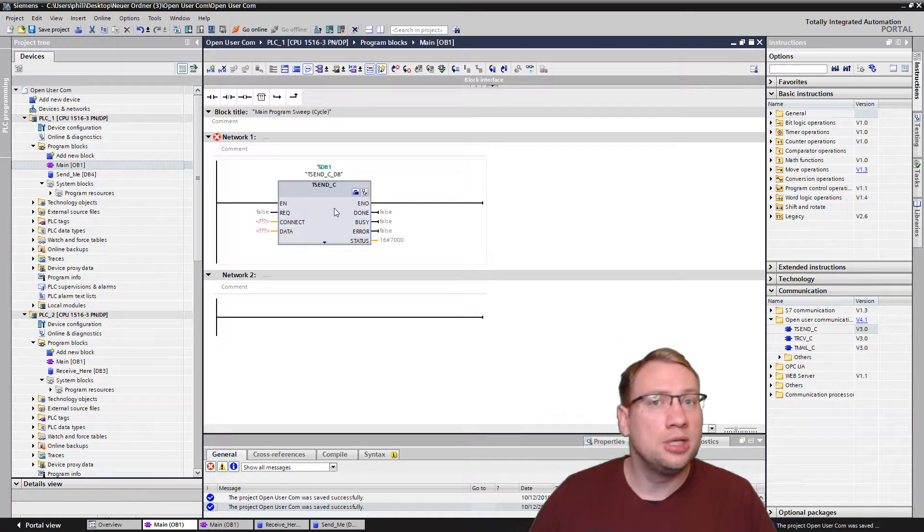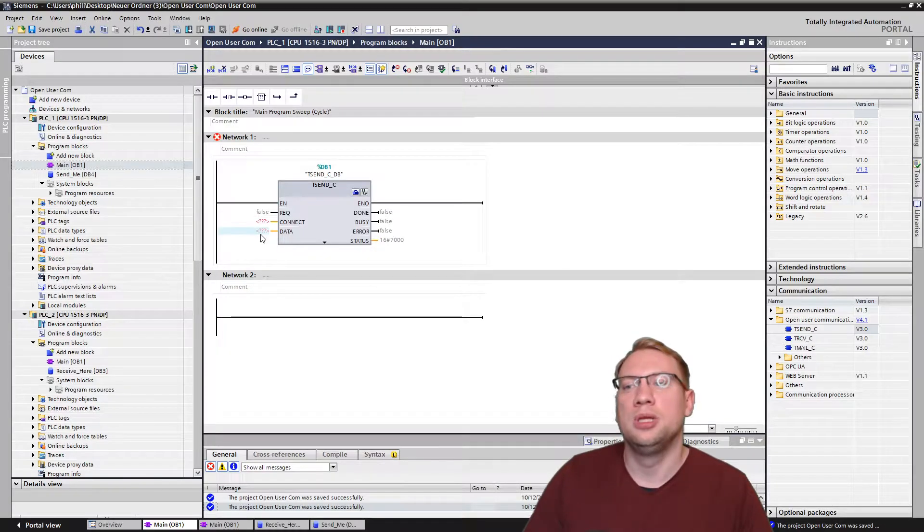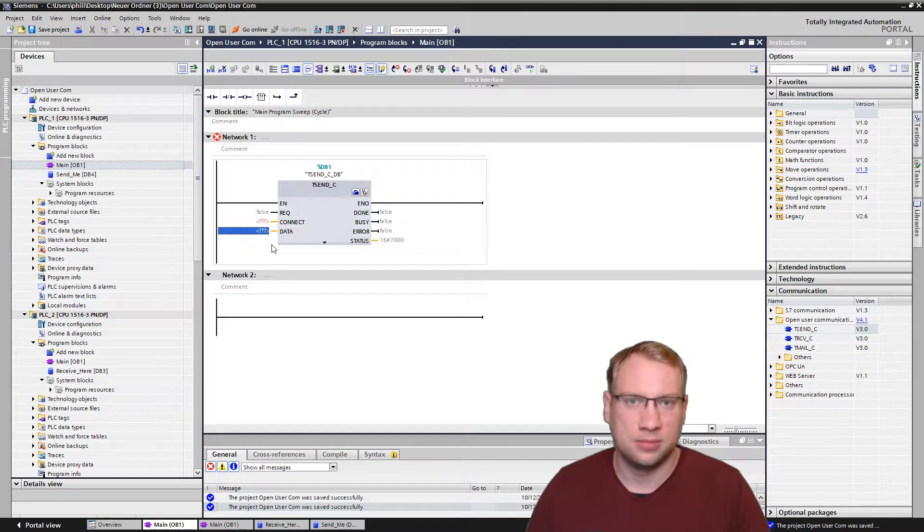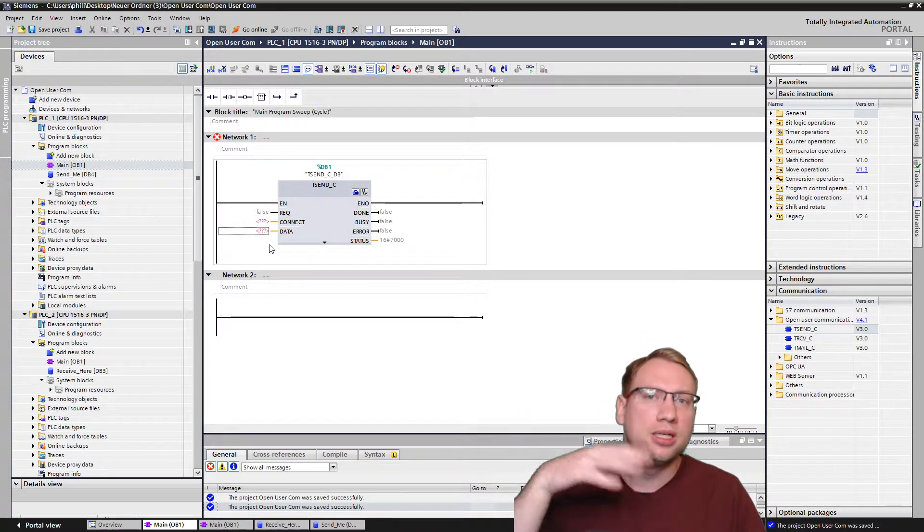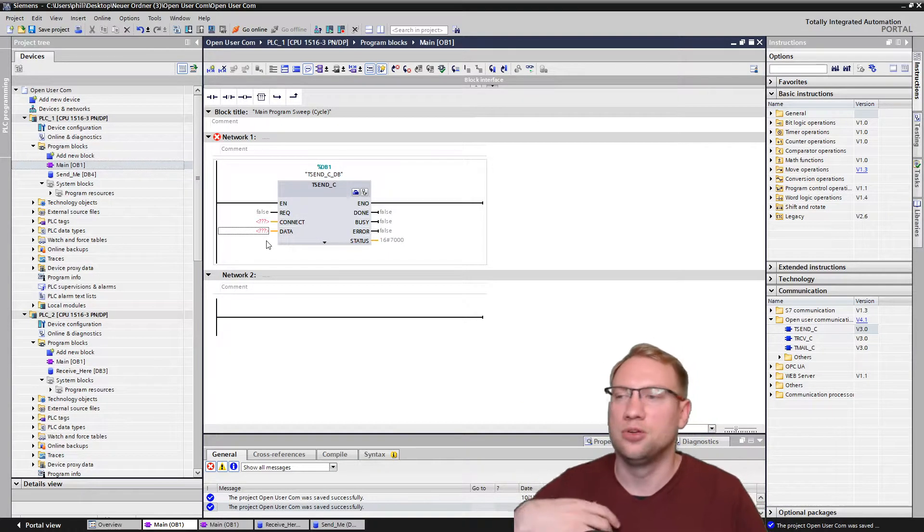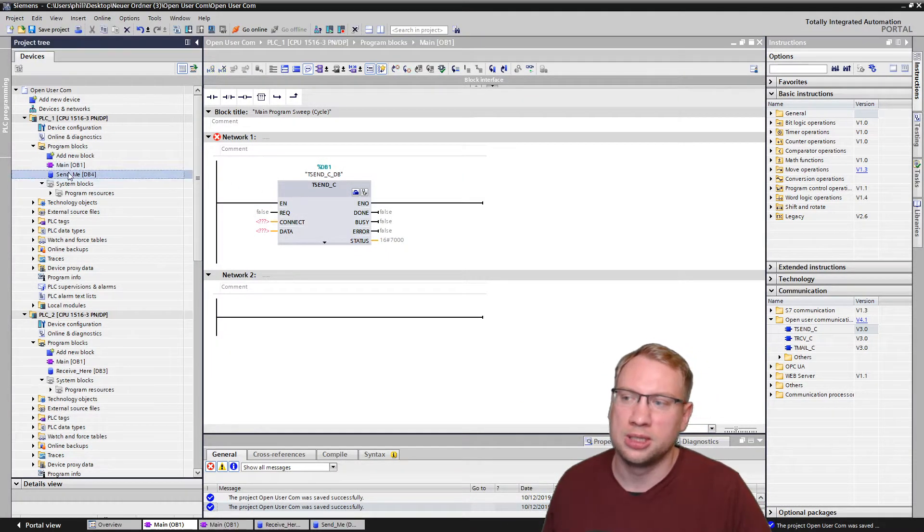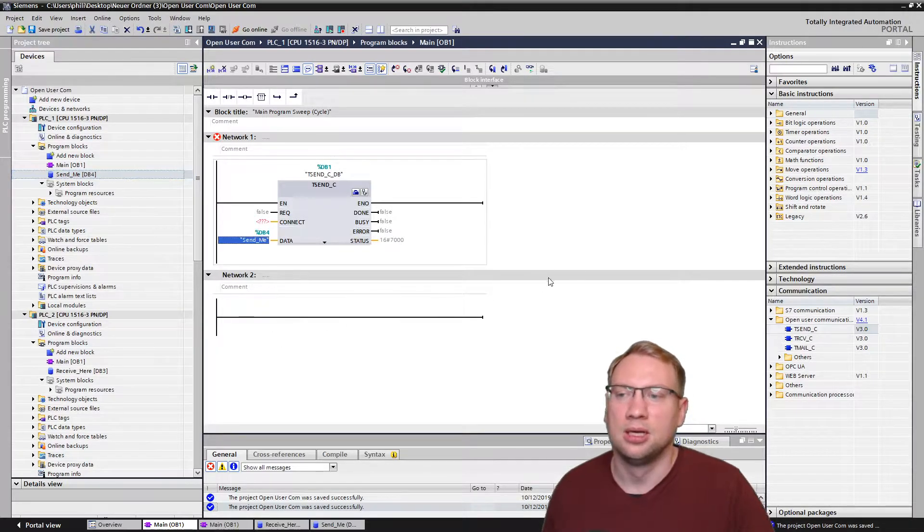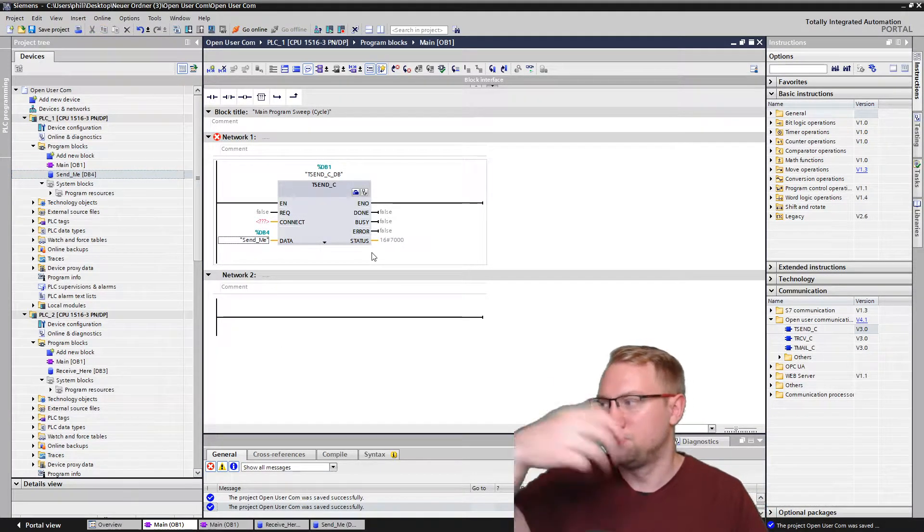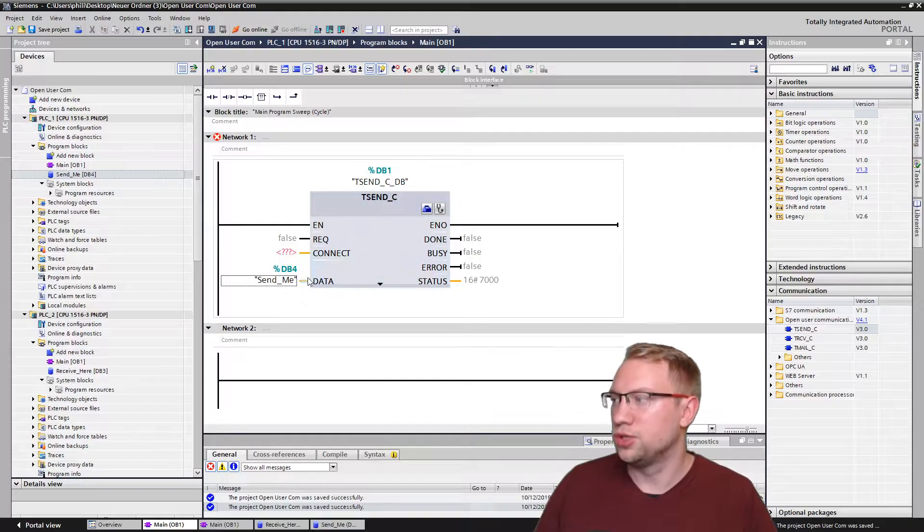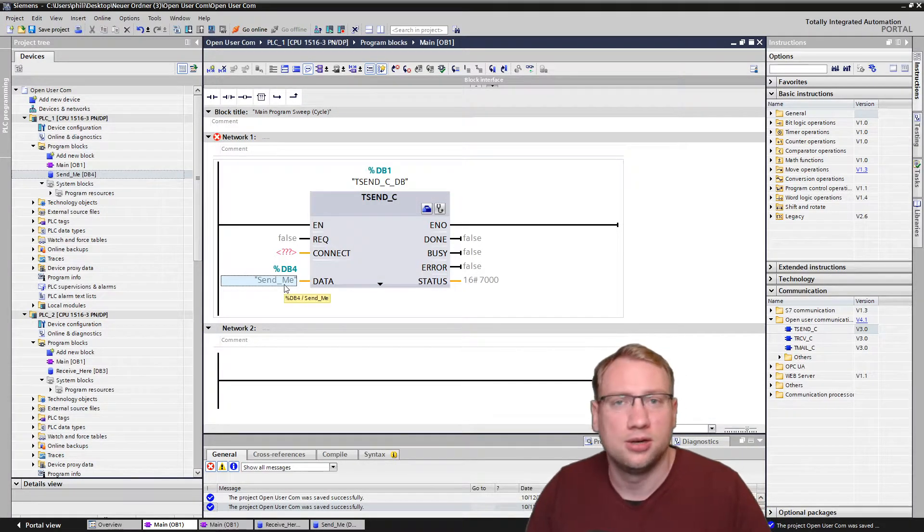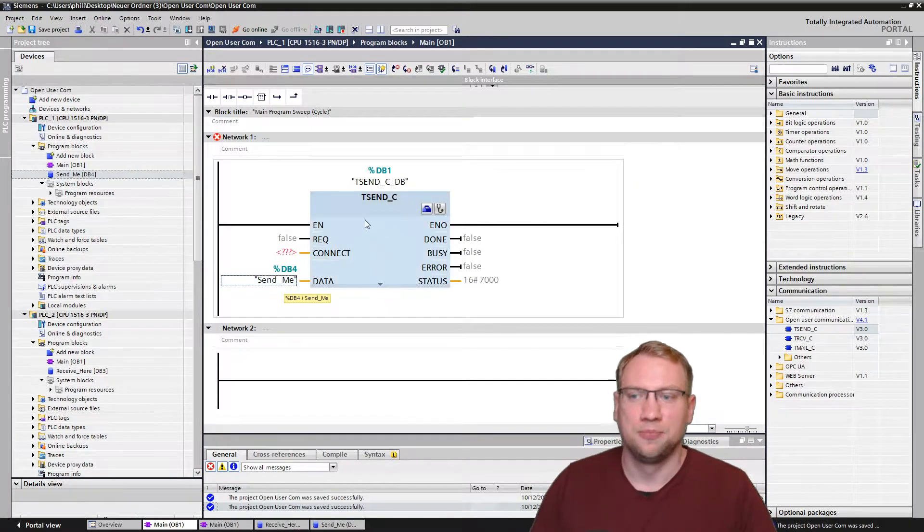On my first PLC that I want to send data from, you find the block that I'm talking about, the TSEND_C in communication. There's open user communication and you have TSEND_C. C stands for compact blocks, so those are compact blocks that have a connection establishment, a disconnecting and the send integrated. I can just put it in here in my program. I will need to make a database because it's an instance of a function block and there we have it. We don't need to put much on here actually. We need data that I want to send. You could put a bit, a byte, a word, one integer value, anything that you want basically. I have this database, the data block that I want to send. I just dragged and dropped it here onto data and there it is. This is what's being sent.